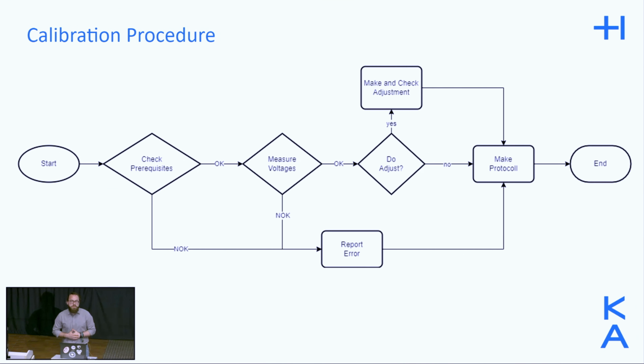For the actual calibration procedure, I derived the procedure from the German national standard, the VDE, to calibrate electrical measurement instruments. And I specialized the general procedure for my purposes. Starting with a quick check of the prerequisites, things like ambient temperature, if all the necessary hardware components are reachable via software. The next step there are the measurement points taken.